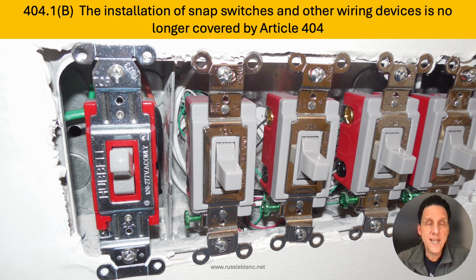Now, general use snap switches like this will no longer be covered by 404. That's going to include dimmer switches, electronic switches, and that door jamb switch I showed you. These are wiring devices. These will no longer be covered by 404. They're going to be covered by another article, and we're going to show you that in a second.